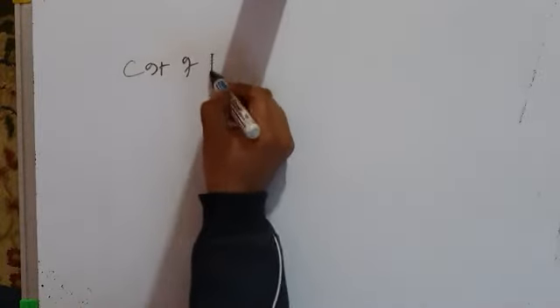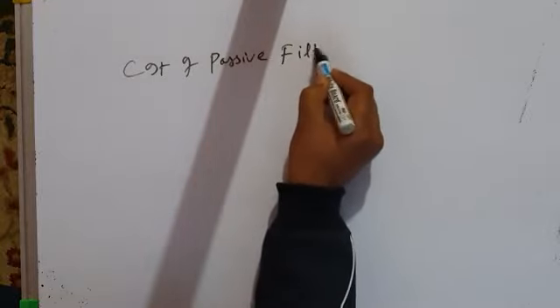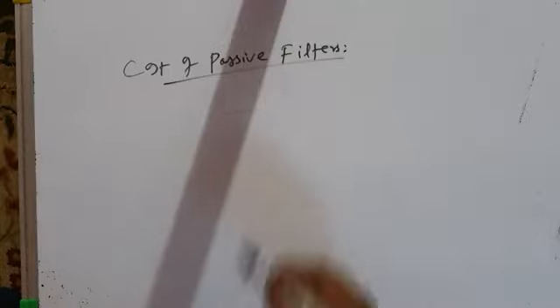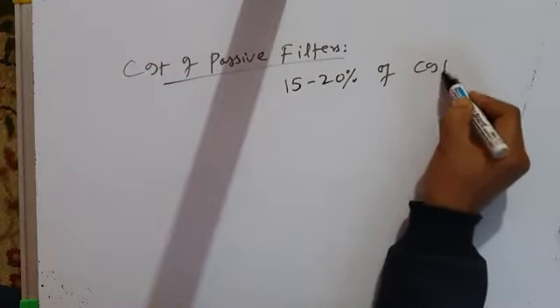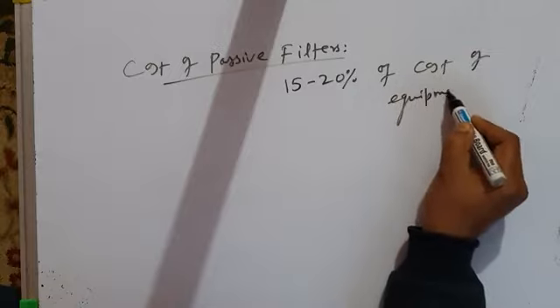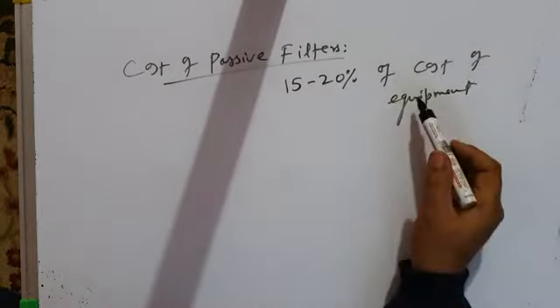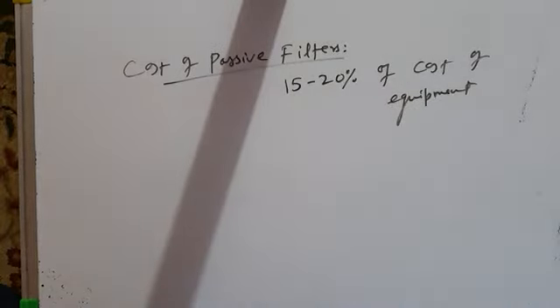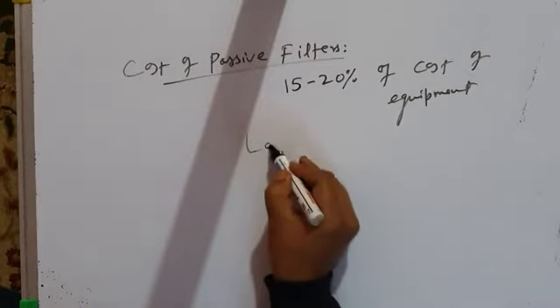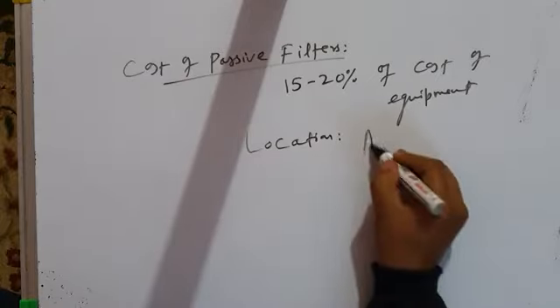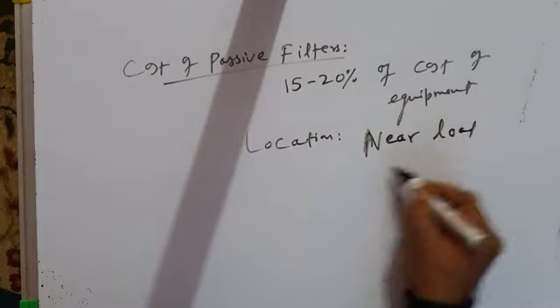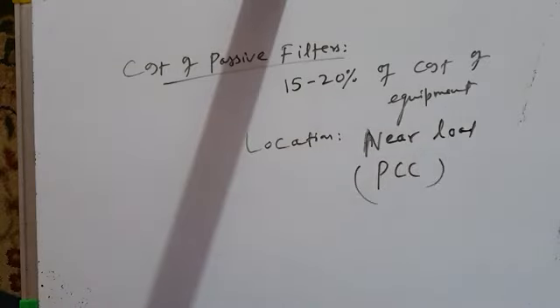The cost of passive filters is an important factor — it can go as high as 15 to 20% of the cost of the equipment, which sometimes becomes unaffordable. Regarding location, the filter should be connected near the load — at the point of common coupling — which is the best place for a shunt passive filter.